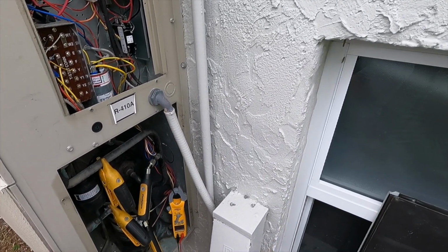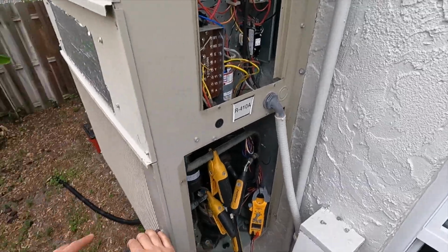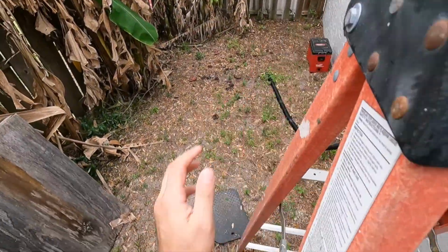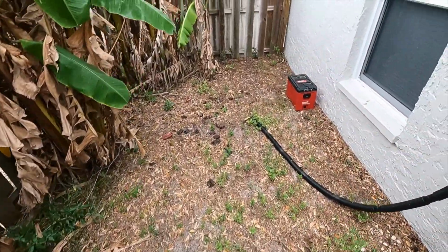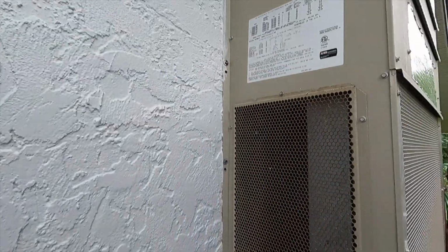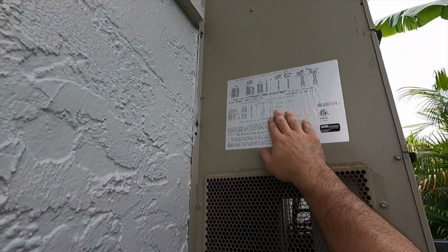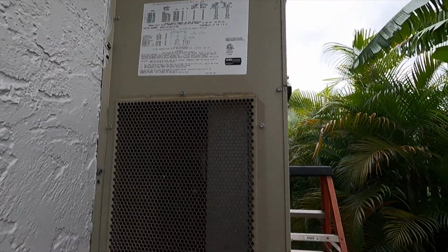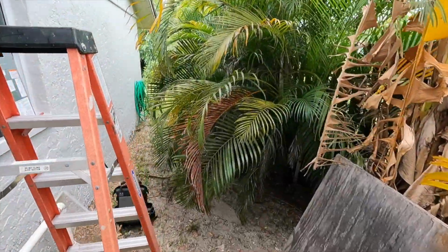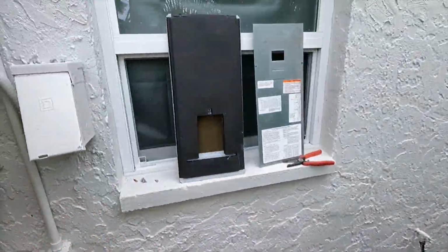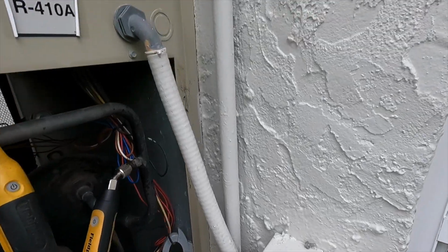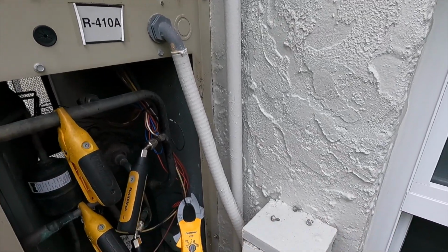But it's important to check the lock rotor amp draw on the compressor because you want to see what the overall health is on start. If we are getting close to the rated lock rotor amps, 112 for this compressor, then we are getting close to that compressor locking up and failing. So we want to give that a quick check.